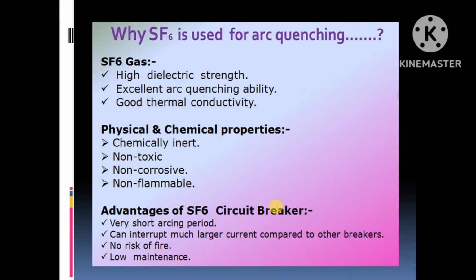Actually, we are using sulfur hexafluoride gas as the arc quenching medium. It has a high dielectric strength, excellent arc quenching ability, and good thermal conductivity. In terms of physical and chemical properties, it is chemically inert, non-toxic, non-corrosive and non-flammable.